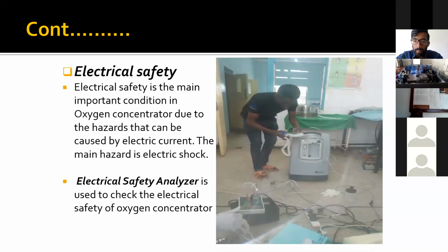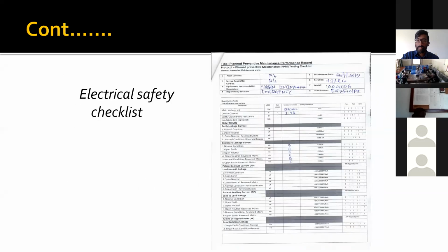Yeah, so the electrical safety analyzer is used to check the electrical safety of the oxygen concentrator. From the picture, you can see one of our champion electrical engineers doing the electrical safety test using the electrical analyzer, which you can see there, the pointer. That is our electrical safety setup which we have at our facility.